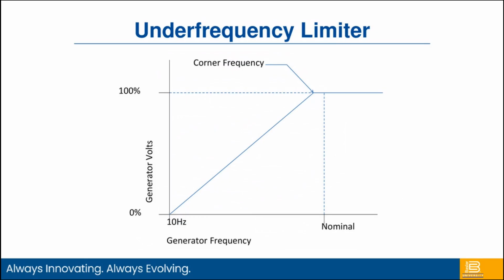We also have an under frequency limiter and a volts per hertz limiter. They're very similar in functionality with a few differences. In this case, this is the under frequency limiter, where I set a corner frequency and a slope, basically. So what this is doing is setting a limit on how much output I can give at a particular frequency. So if my frequency is not at 100% or not at optimal operating range, I want to limit the amount of excitation, or the amount of voltage, I'm going to allow the machine to build to. So I'm really taking my set point and backing it off.